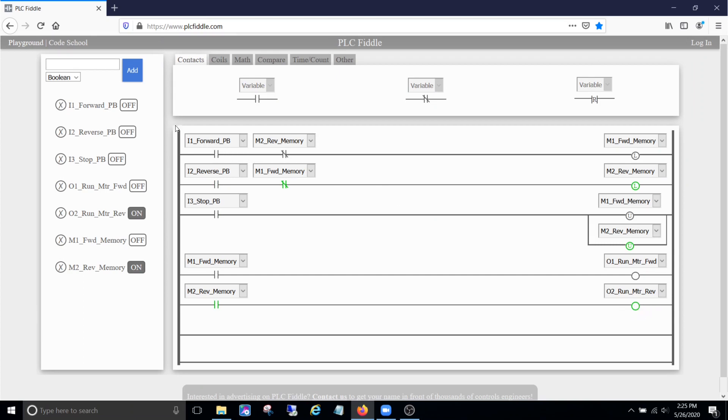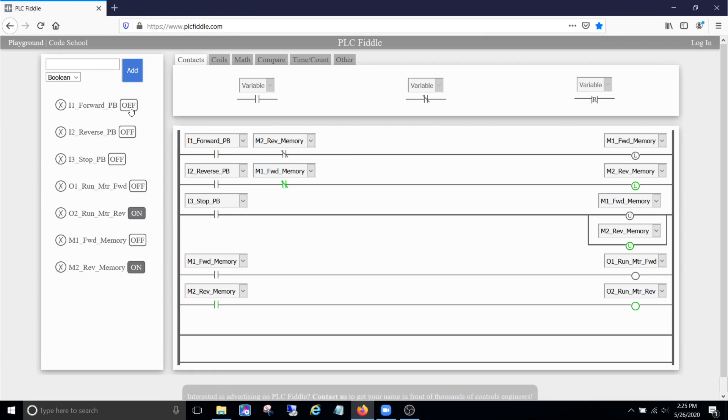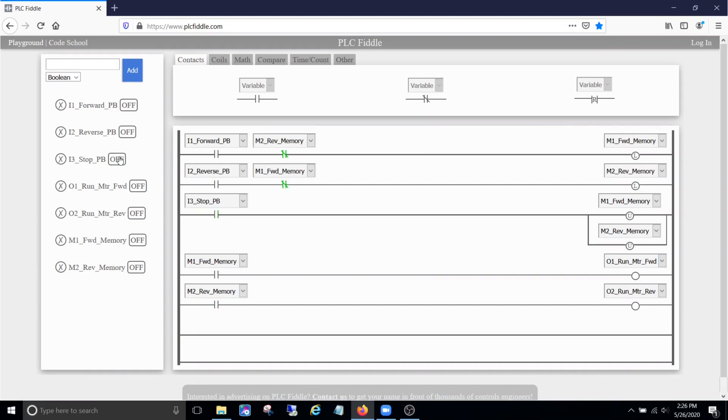But when I press forward, this normally closed contact of this reverse memory is blocking it, right? So the logic can only flow to right there, it can't go any further. So same thing, doesn't matter how many times I press forward, it's not going to pass this normally closed contact, and it's going to run reverse until I hit the stop push button. Then it'll stop it.